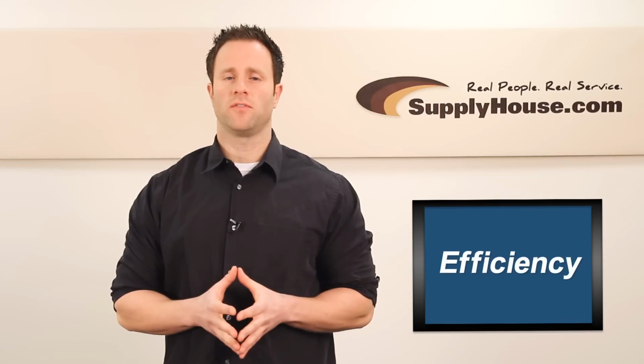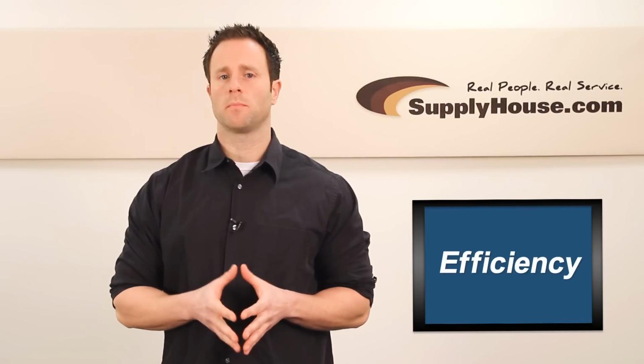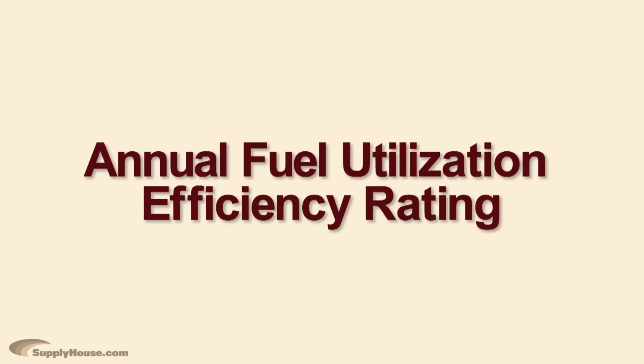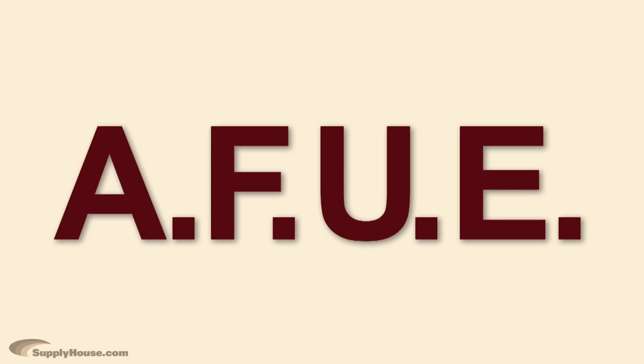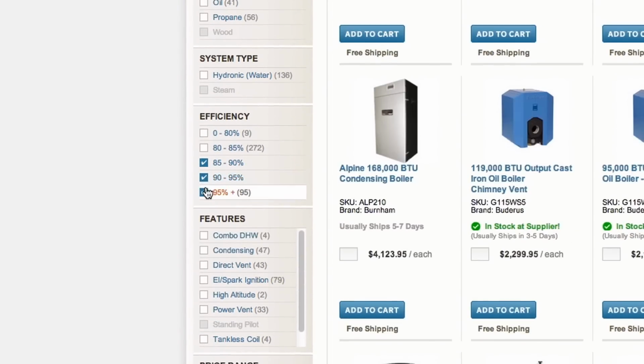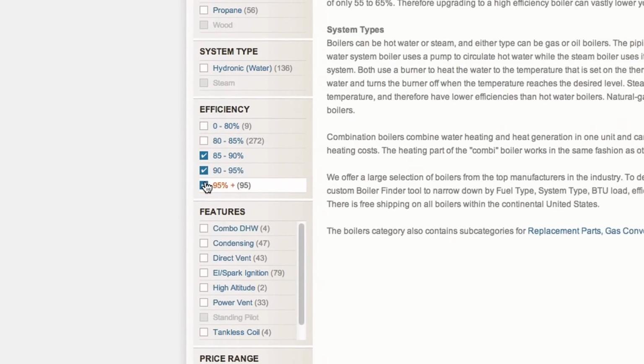A boiler's efficiency rating depends on how much fuel it uses to burn a specific amount of heat and how much fuel is wasted. The Annual Fuel Utilization Efficiency Rating, or AFUE, expresses the efficiency of a gas or oil boiler. Any boiler with an AFUE rating of 85% or higher is considered to be a high-efficiency boiler.